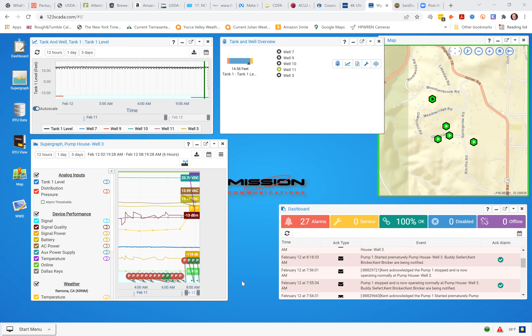Would it make sense that, should we ever have to replace well 11, we change it out to a variable speed motor to regulate the flow so you don't have that high back pressure? I think it would be an unnecessary complication. We've never had a motor failure ever that I recall, Tim. We've had pump failures galore, but never a motor failure. So I don't think it really matters, turning it on suddenly and wrenchingly. It seems to work all right. The pump can take it, it's designed for that. And our electronics at the wellheads are pretty simple, and we have motor savers to watch over the whole process. It all seems to work very well.